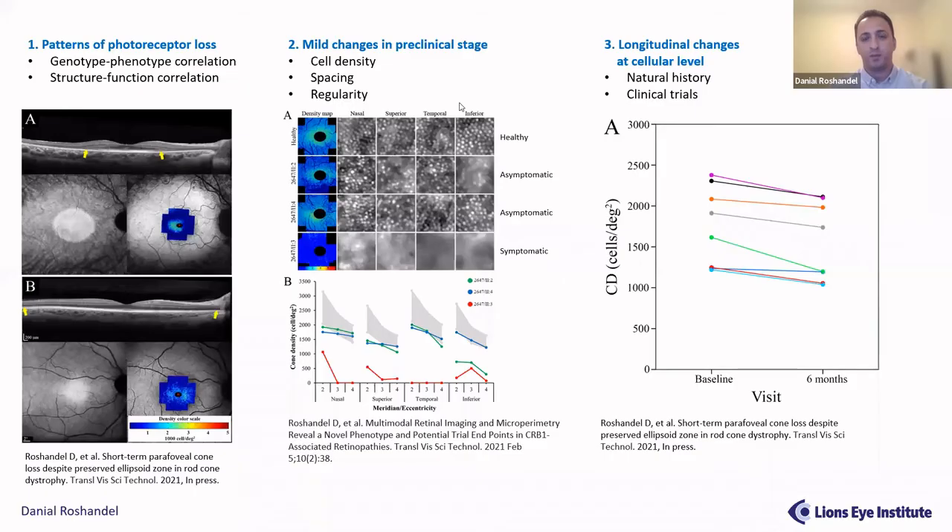Hello everyone, thanks for having me. We are using the RTX1 for adaptive optics imaging of patients with IRDs for several purposes. The first is to determine the patterns of photoreceptor loss, because we can see photoreceptors using adaptive optics which is not possible with OCT. We use these images for genotype-phenotype correlation, which is very important to us. If you also have functional tests like microperimetry or multifocal ERG, you can use AO for structure-function correlation studies.